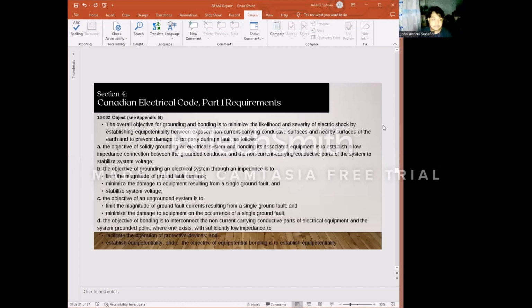Next is the objective of bonding: to interconnect the non-current-carrying conductive parts of electrical equipment and the system grounded point, where one exists, with sufficiently low impedance to facilitate the operation of protective devices, and establish equipotentiality. And the objective of equipotential bonding is to establish equipotentiality.